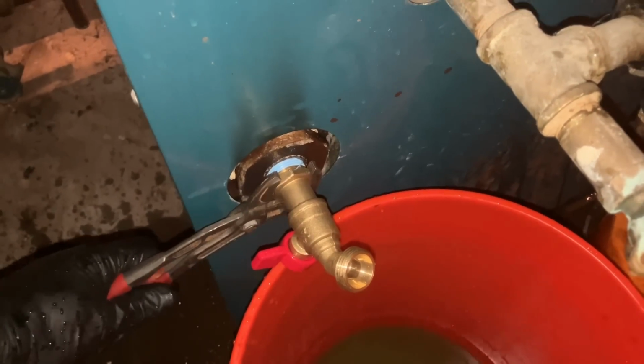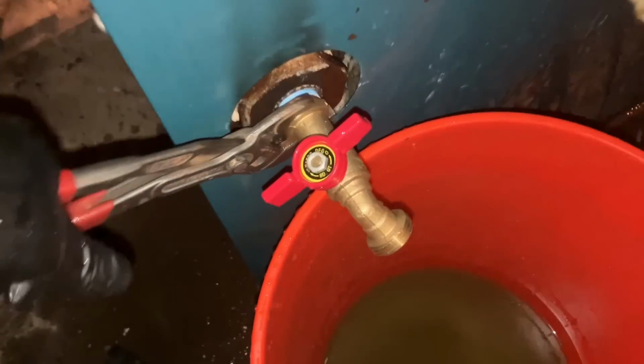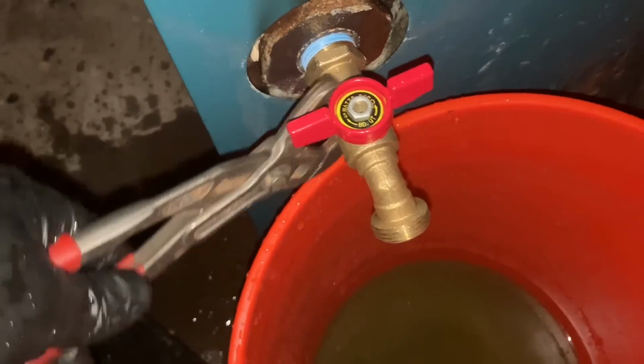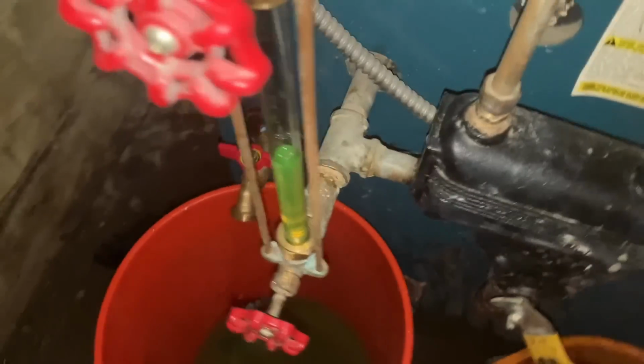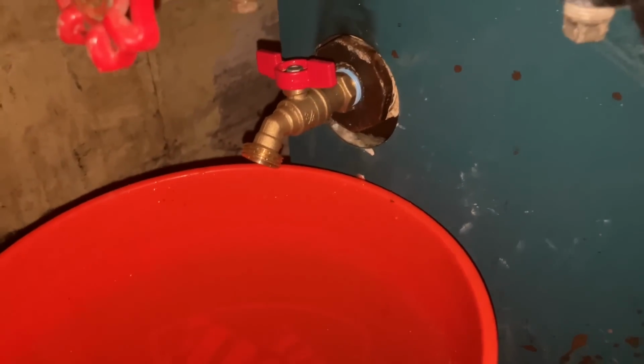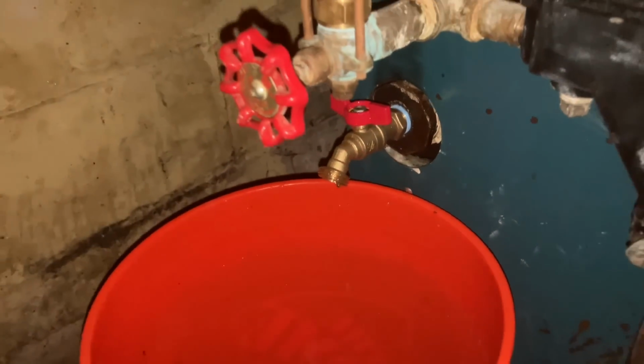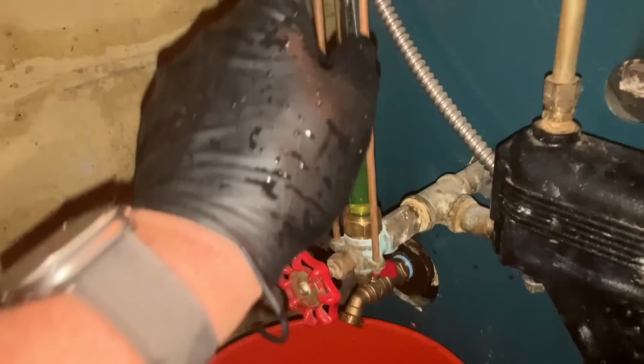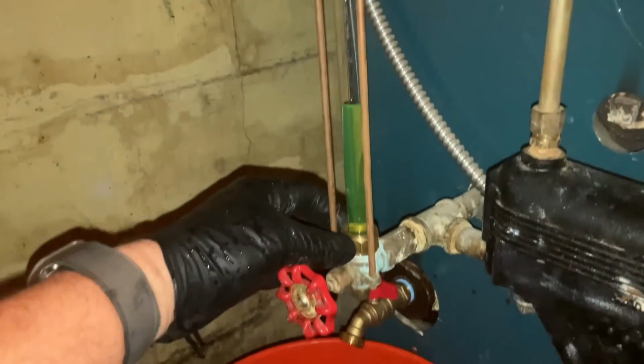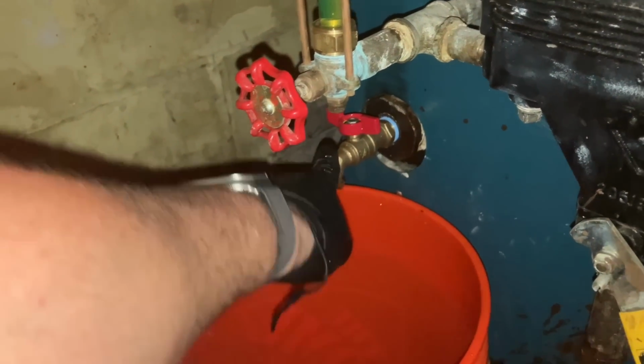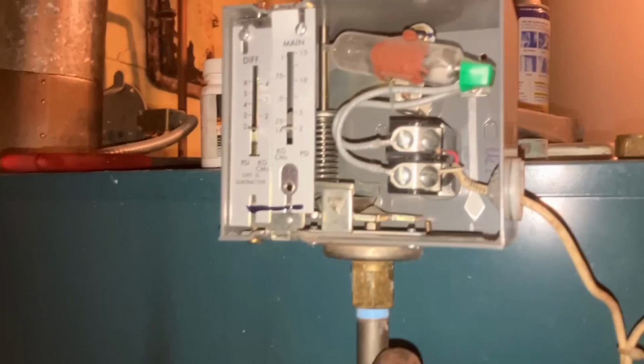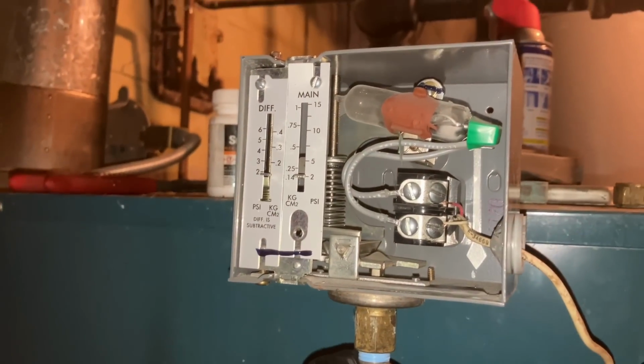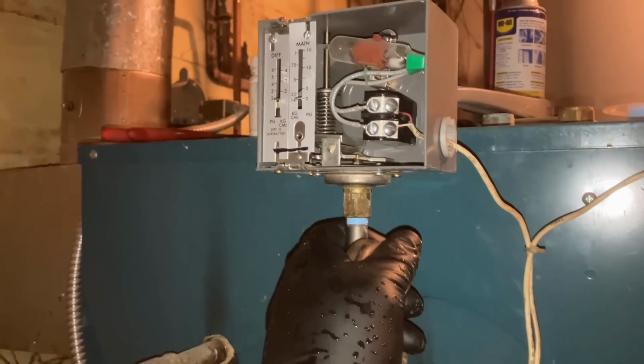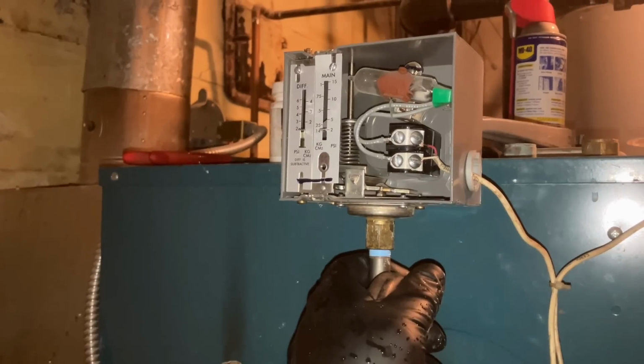So now we have a solid, reliable quarter-turn valve by an American company called Watts. I was going to get the Bluefin. I saw it sitting there in the truck, but we'll let China stay in China. Okay, we now have a new sight glass, the sight glass rings, nuts, and washers, and a quarter-turn valve on the drain. We have a clean boiler, a clean pigtail, and the pressure control is set to where it needs to be set. All we need to do is turn on the power to the boiler and go a la peanut butter sandwiches.